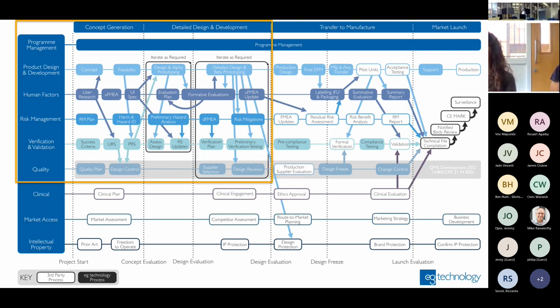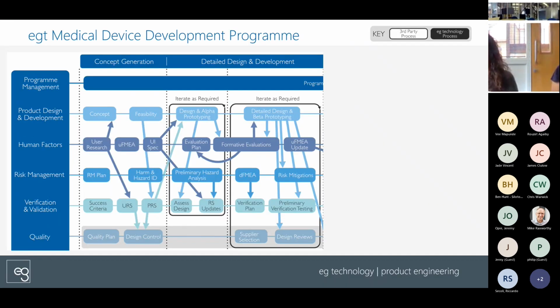I just want to zoom in on this early section for a minute. As you see, the usability side of things starts with the user research, and that feeds into your URS, your user requirement specification or user needs, which falls under the verification and validation section, and that helps you define your product requirements, which feeds into your design. And I'm going to talk a bit more about requirement specifications and traceability in a bit. That's an important area where it overlaps.